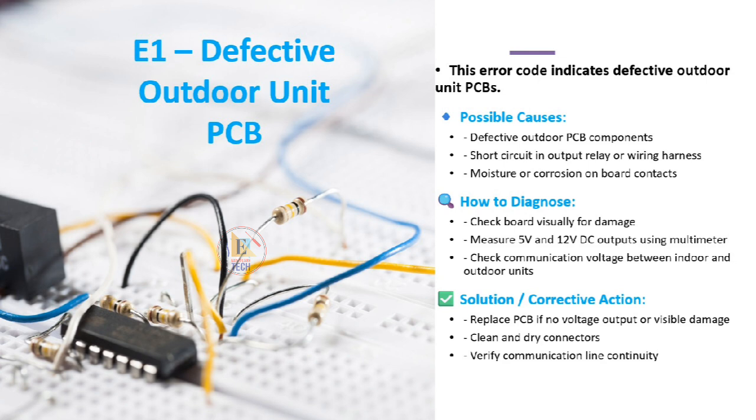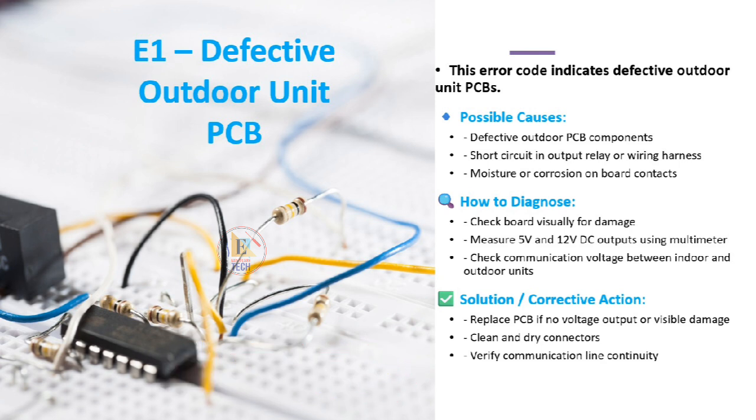Error code E1 indicates a defective outdoor unit PCB. This fault is commonly caused by damaged PCB components, short circuits in the output relay or wiring harness, or moisture and corrosion on board contacts.